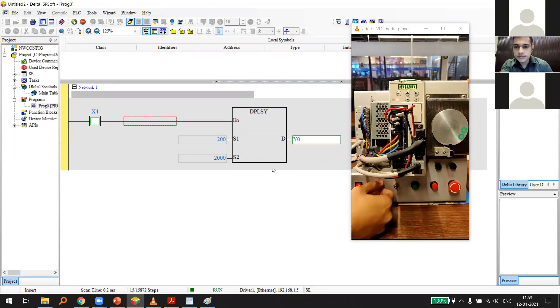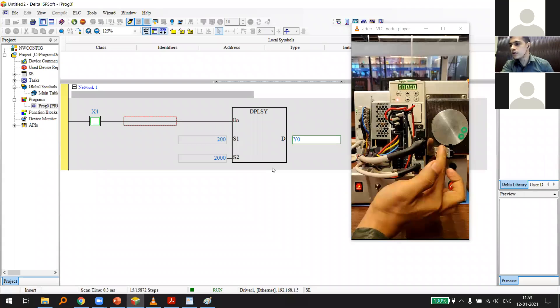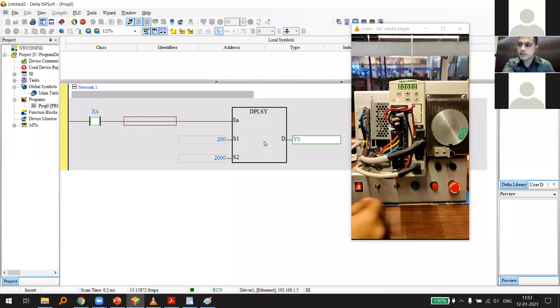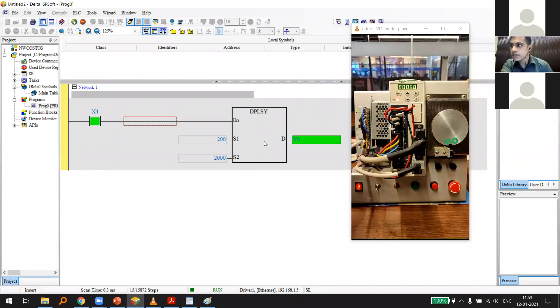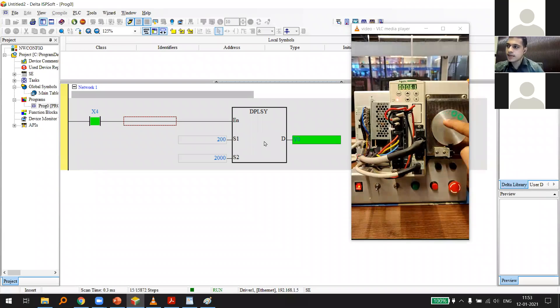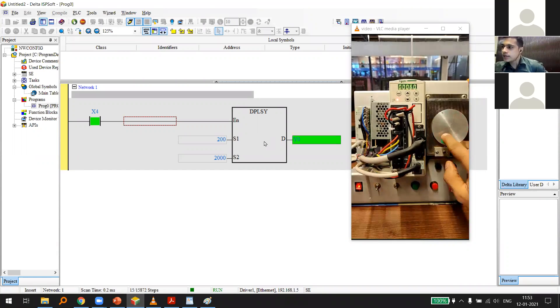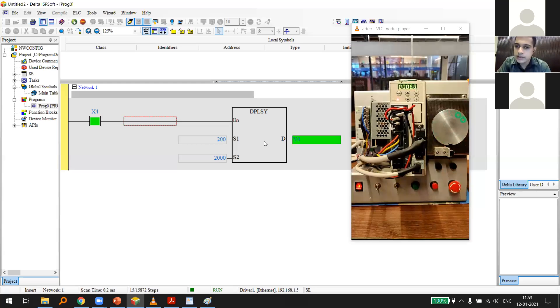I'll activate the contact to start the instruction. You can see 6.0 RPM displayed here, and the servo rotates exactly one revolution and stops right back where it started. Running it again, it stops at the same point — this demonstrates the repeatability of the servo drive and motor.